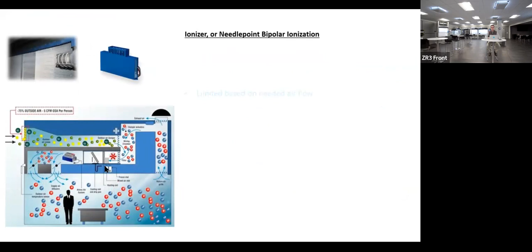The next technology is ionizers, or needle point bipolar ionization. These are being sold as hydroxyls, or the magic pixie dust that just emanates through the HVAC system and disperses these negatively and positively charged ions to deactivate, capture and kill any particle or bioaerosol present in the facility. Doesn't work. This technology was intended to be used in areas of close proximity, such as an ice machine, or inside the HVAC system to deactivate anything going to the coils or even the filter itself in the HVAC system, but it will never address the air.